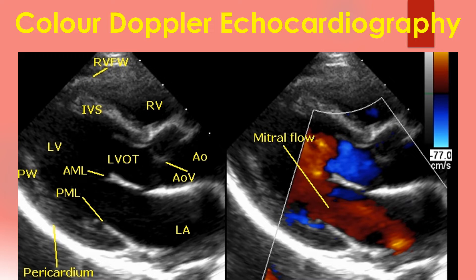Displaying Doppler flow information on a two-dimensional image is known as colour flow mapping or colour Doppler imaging. Here one image is two-dimensional and another has colour flow information in a sector. Blue colour represents flow away from the transducer and red represents flow towards the transducer. It has nothing to do with the colour of the blood, like oxygenated or deoxygenated.